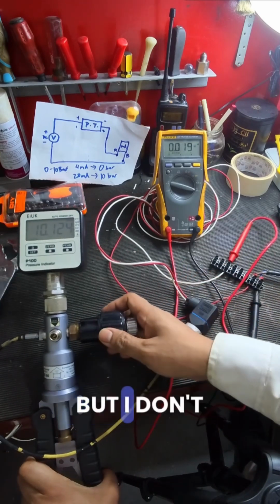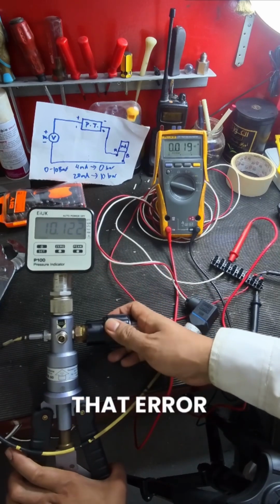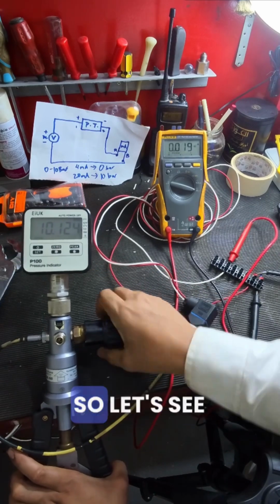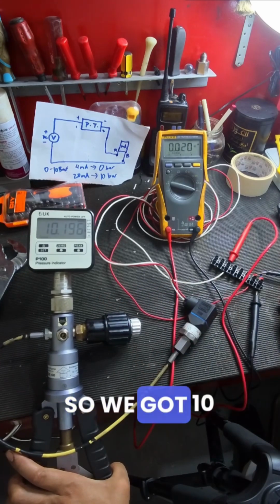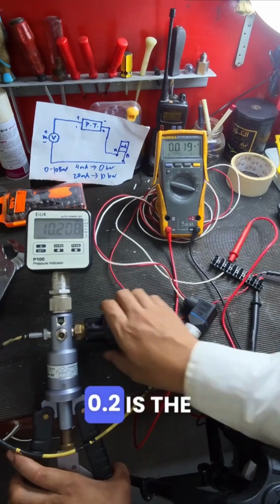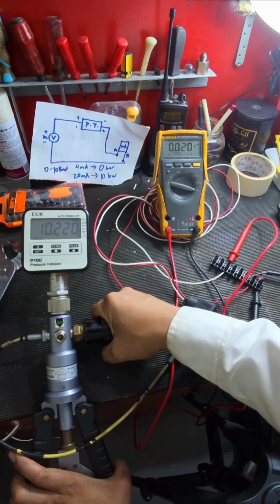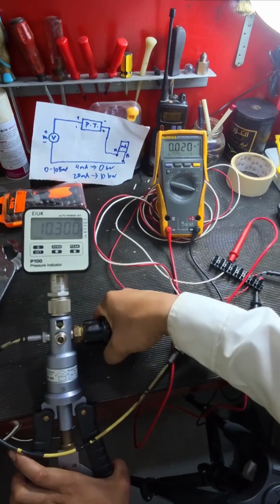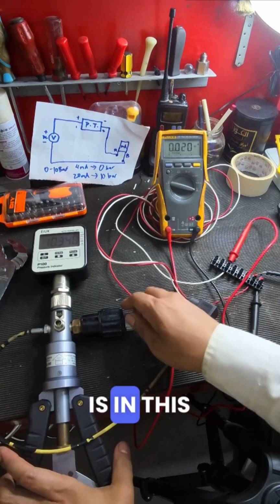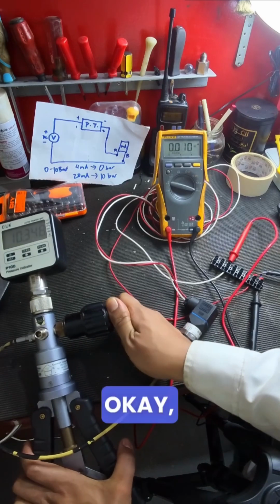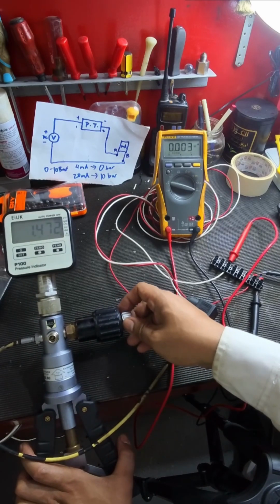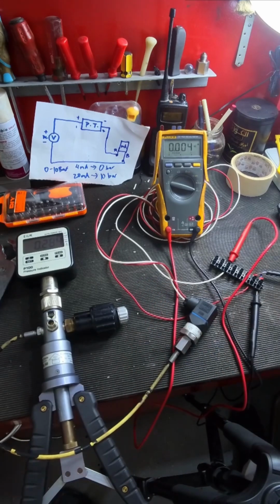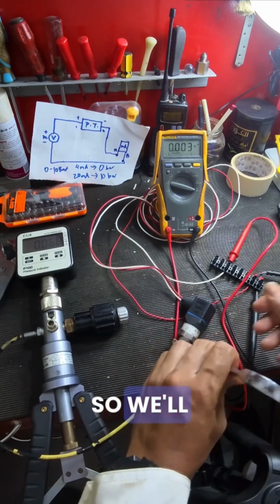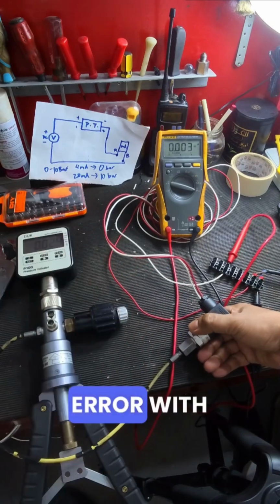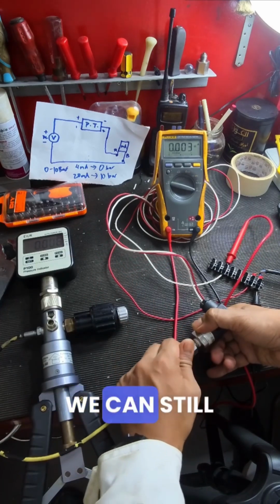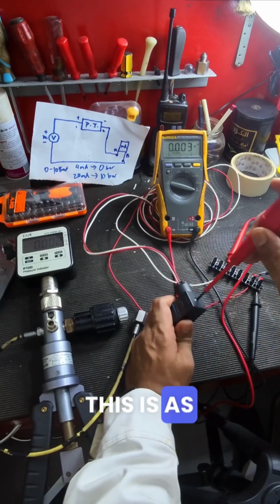There's only a differential, but I don't know how much. I also don't know how much error this calibrator has on the pressure. So we will see. Okay, we got 20 milliamps output at 10.2, so 0.2 is the error. So this one can still be used. But I believe 3 milliamps at 0 pressure will not be good for the PLC, so it will give some abnormal error. But in an emergency we can still use this one, so maybe this is a backup.